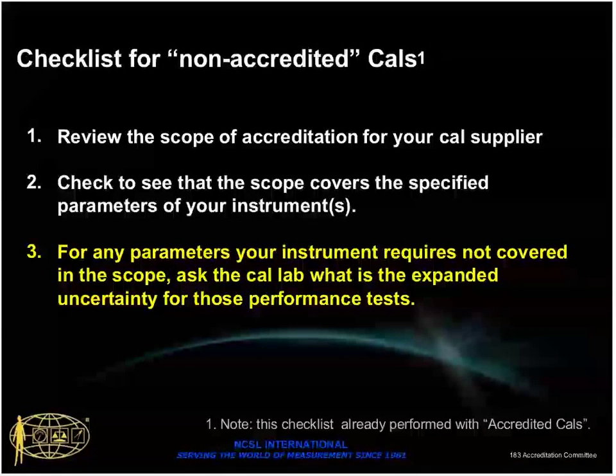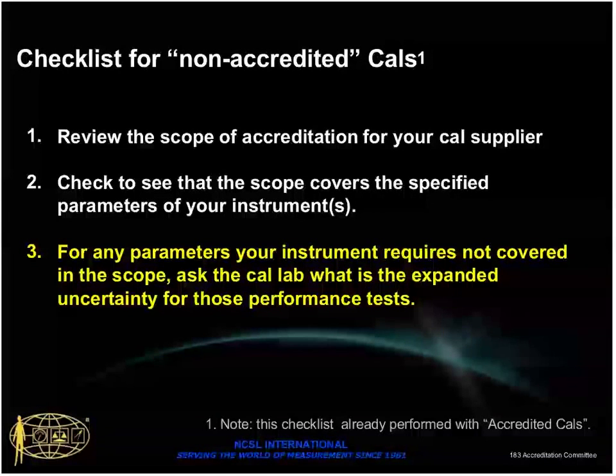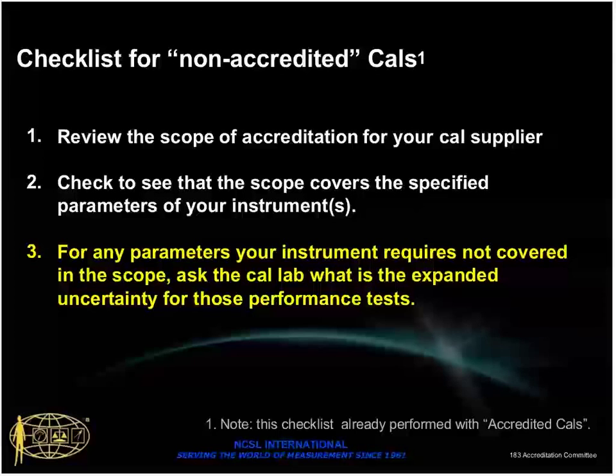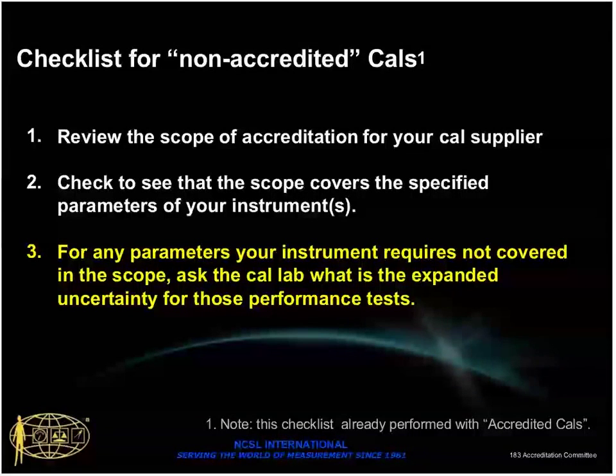And in the scenario where a supplier offers calibration service which is outside of their schedule of accreditation, then if I were in that situation, I would ask that calibration lab, all right, for this instrument model XYZ, what is the expanded measurement uncertainty that I can expect for this instrument? Now, if you're not used to asking that question, you might wonder how reasonable it is. And I can tell you from my company's standpoint, that's a very reasonable question, and it's a very simple matter for us to go get a sample calibration report, pull that up, and share that with you and say, well, here's a same model for a different customer.